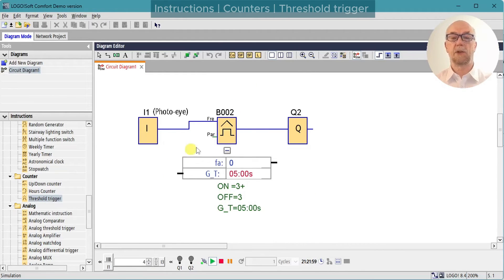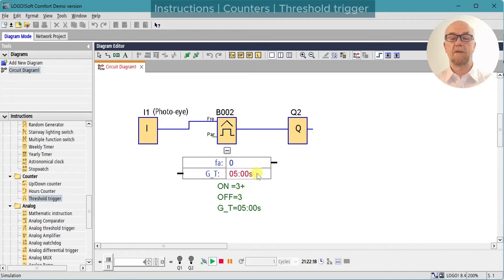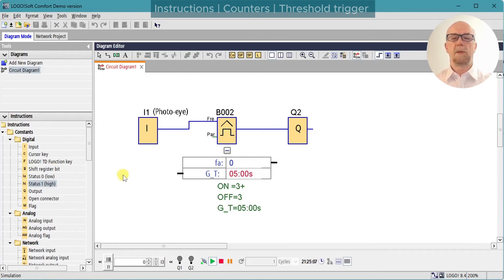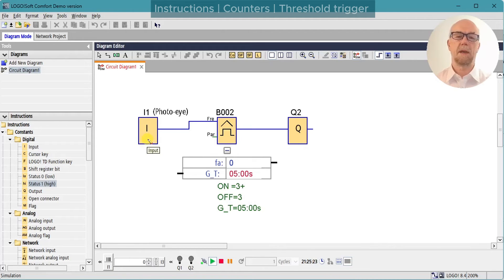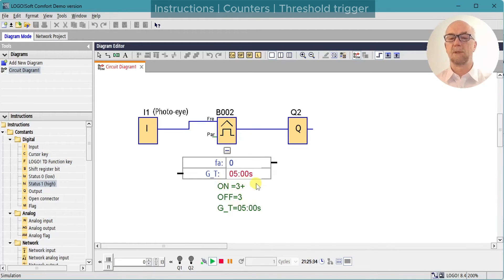I've set up a second threshold trigger running from a low-speed input. Input 1 is one of the analog inputs so it doesn't support high-frequency reading. The threshold is set for three pulses with a gate time of five seconds, so if we get three pulses within the five-second gate the output should turn on. After a series of pulses the FA value shows a frequency of 6; with no more pulses, five seconds later it resets to zero. You could use a photo eye counting boxes on a conveyor to turn on if more than three boxes pass in five seconds, but there's no way to synchronize this with, for example, the first box, so it's of limited use.